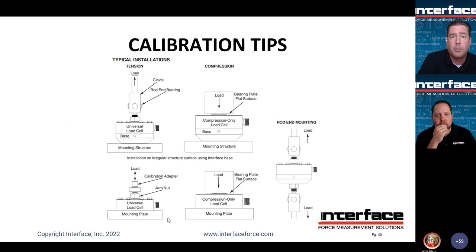So this is just a good example. This is from our install sheet. This is a kind of a summary of the different configurations we see of load strings. So on the left here, you see kind of a more conventional loading configuration, where this would be great for tension calibration. You've got a rod end bearing installed, and then adapting through a clevis into the load string. Directly to the right of that would be a compression only example, where we have some sort of a flat platen that's fixtured into the load string, pressing against the load cell. It's tough to see there, but on that specific load cell, this is an example of a spherical surface for a single point of contact. In between that loading platen and the compression load cell is a spherically radiused loading button. So again, single point of contact.